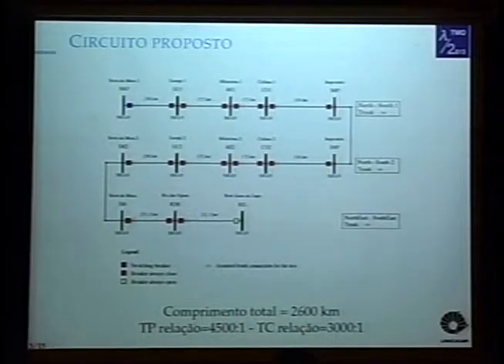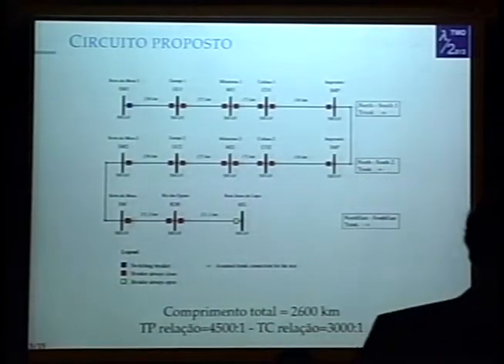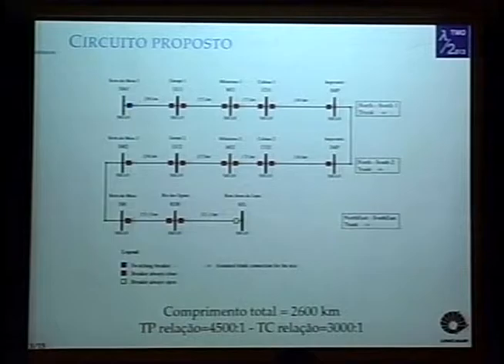So the proposed circuit is also well known. We have to use the 3 trunks of the Brazilian electrical system. The sending terminal is the substation of Serra da Mesa 1, and the receiving terminal is the substation of Bom Jesus da Lapa, whose circuit breaker is always open because we have a no-load energization test. For maneuvers, we can only use the circuit breaker in Serra da Mesa 1.